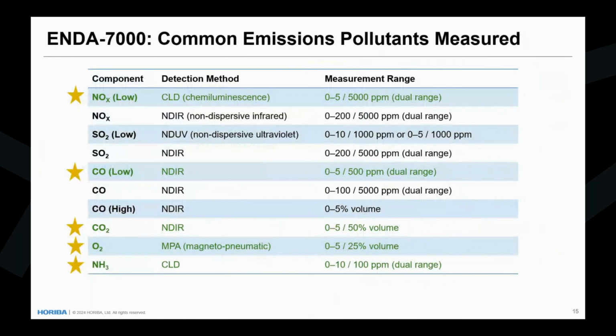There are a number of measurement ranges that the ENDA-7000, the PG 300, and the VA 5000 can be configured to. Based on the estimated or known performance of the emissions generator, gas turbine, backup generator, or diesel generator, we configure that analyzer with the appropriate measuring range to capture complete and accurate data for that customer. We customize those ranges based on known information about the turbine and the data center's equipment, as well as what pollutants the reporting agency is looking for.